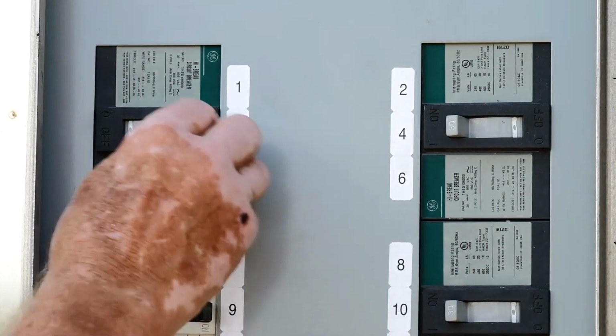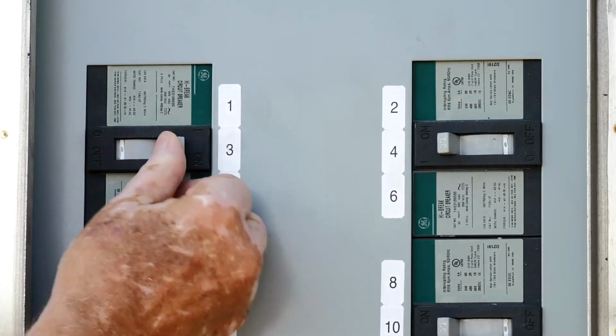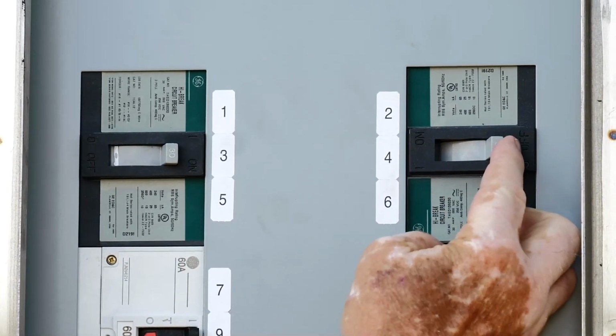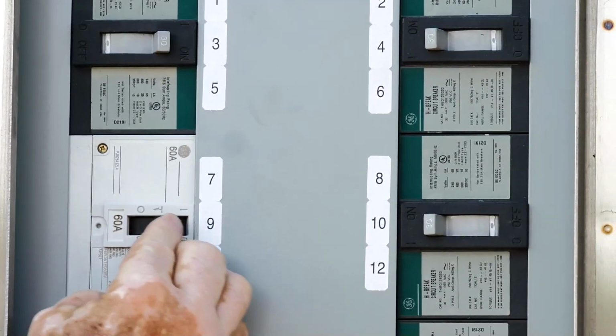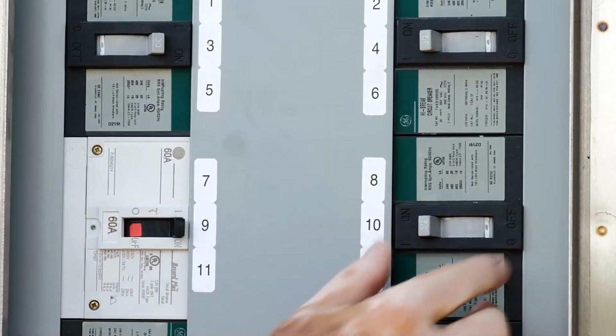Circuit breakers are not to be used for continuous controlling of your lighting system. There's a misconception that circuit breakers that are labeled SWD or HID are rated for switching. And they are, but not for continuous switching for daily operation of lighting systems. They are intended to be able to break the circuit under load for routine maintenance, which takes place periodically.